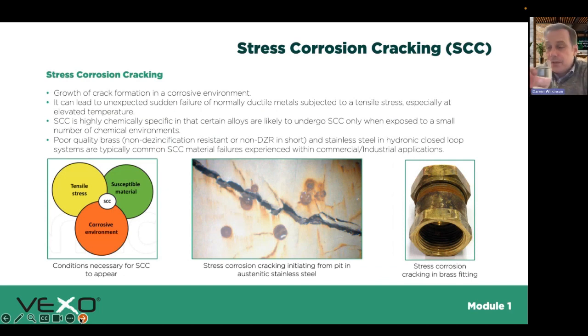And then there's stress corrosion cracking. It doesn't come up as often as the other issues of corrosion, but typically in our industry, you'd see it mostly on chill water systems. Rather like the fire triangle, to have a fire you need a fuel source, you need heat, and you need oxygen. If you take one of those away, you won't have a fire. Stress corrosion cracking is rather similar. You need a tensile stress. So we've got a hydronic closed loop system under pressure. We've got connections that have been threaded and are under pressure where those joints have been made.